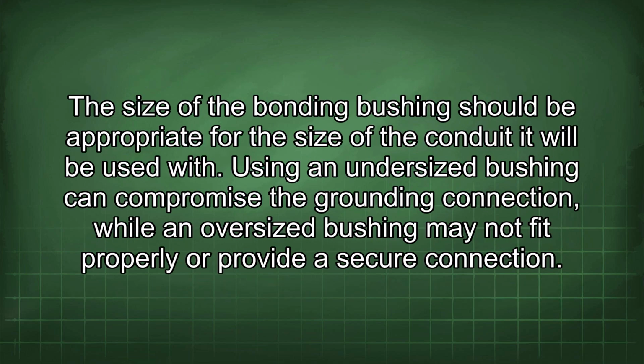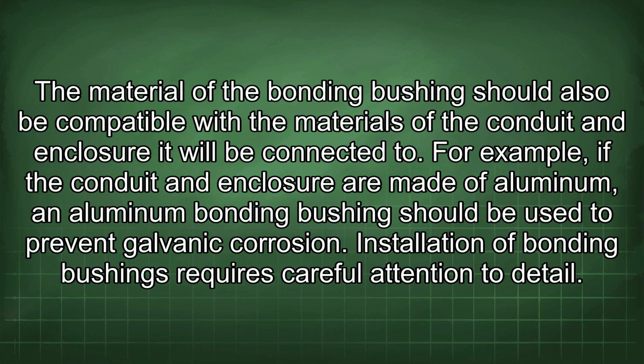The size of the bonding bushing should be appropriate for the size of the conduit it will be used with. Using an undersized bushing can compromise the grounding connection, while an oversized bushing may not fit properly or provide a secure connection. The material of the bonding bushing should also be compatible with the materials of the conduit and enclosure it will be connected to. For example, if the conduit and enclosure are made of aluminum, an aluminum bonding bushing should be used to prevent galvanic corrosion. Installation of bonding bushings requires careful attention to detail.